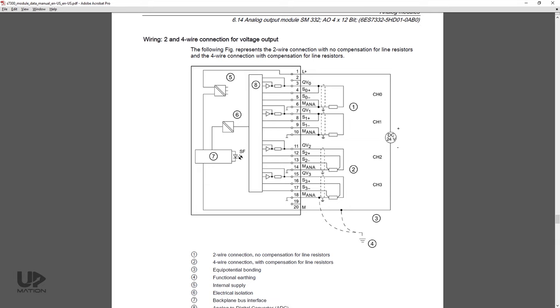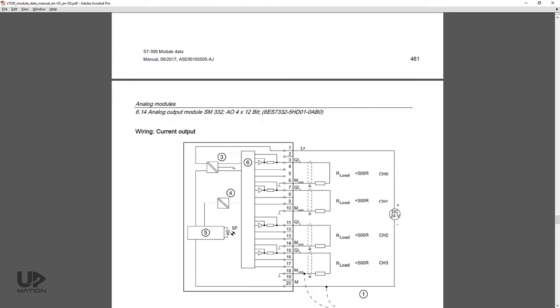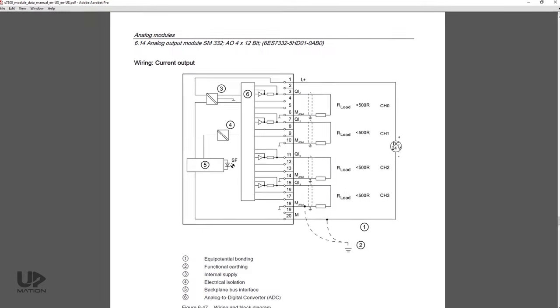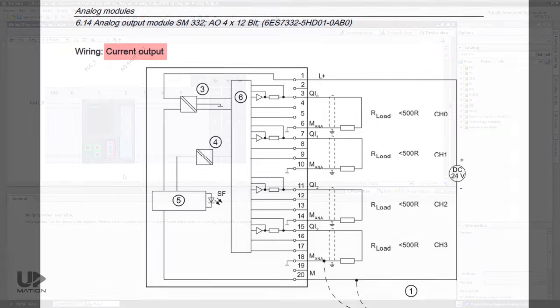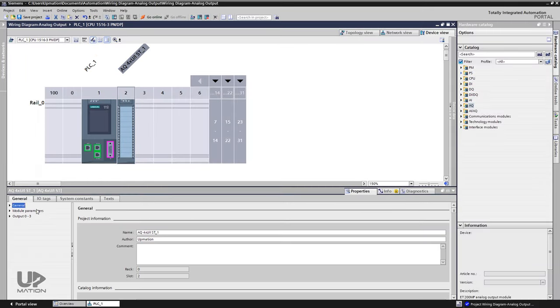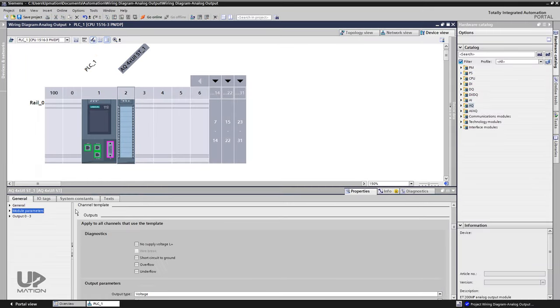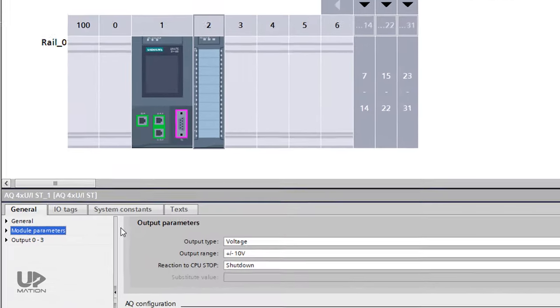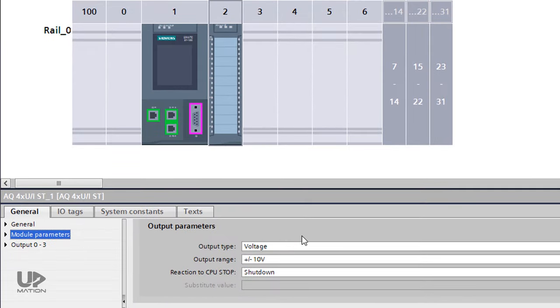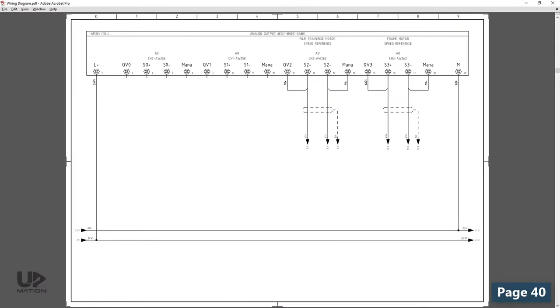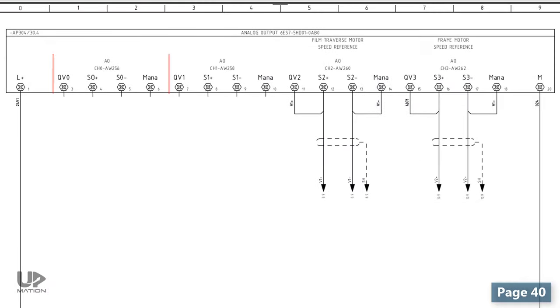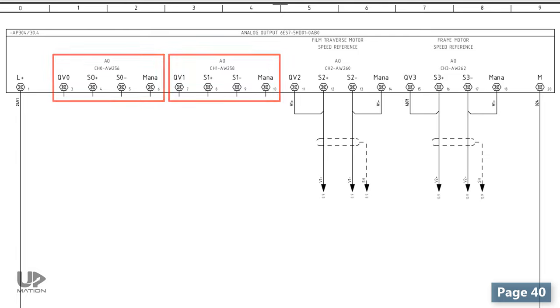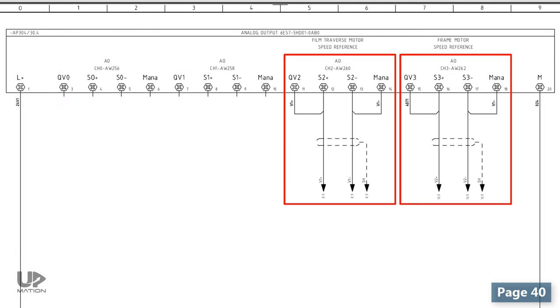The wiring diagram for the card will be different if we decide to use the current output format. The PLC programmer can adjust the settings in the software to specify whether it would be a voltage or current type of output. In the main wiring diagram, the first 2 channels were left empty and channels 3 and 4 have been occupied.